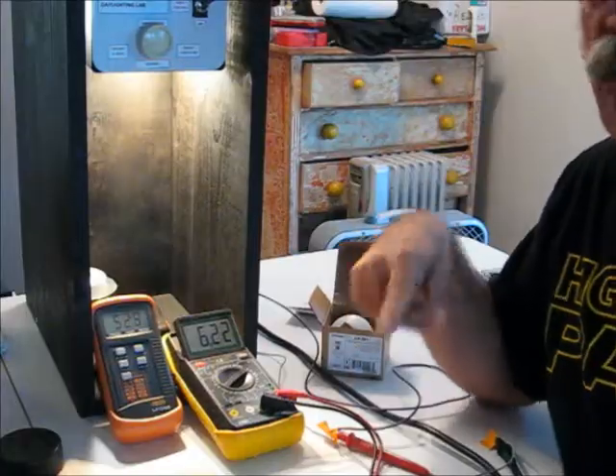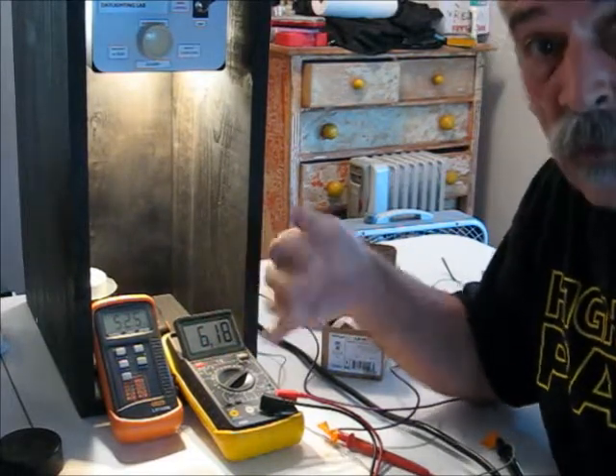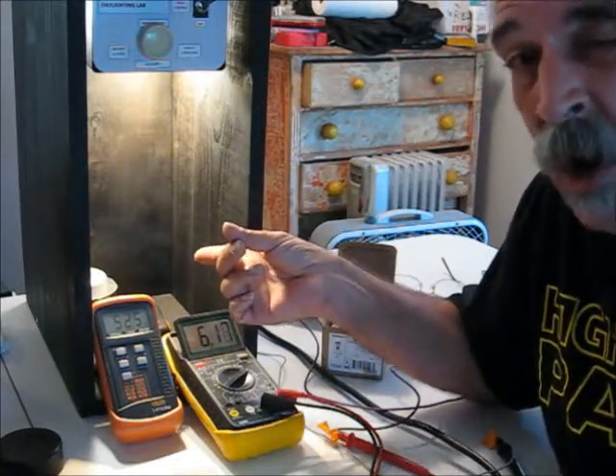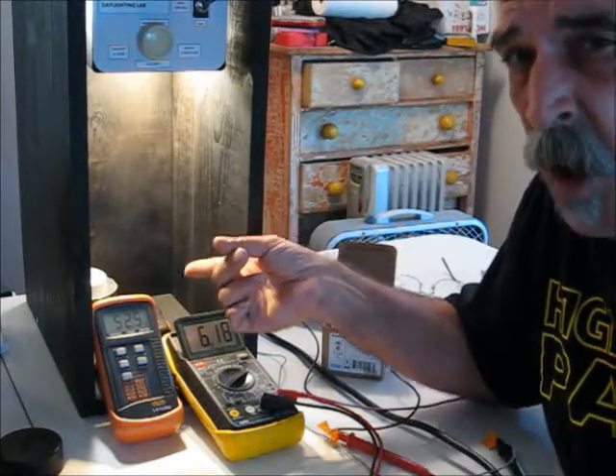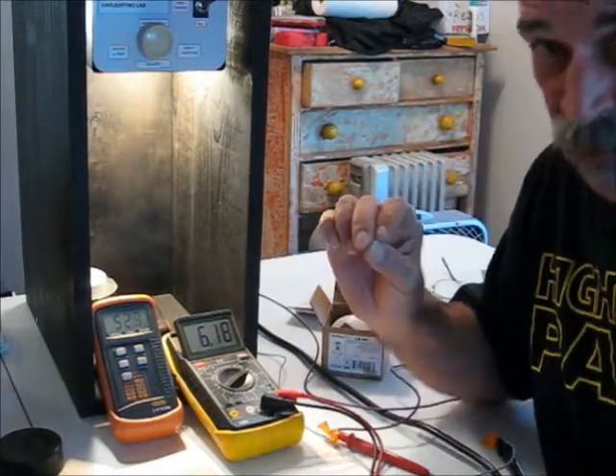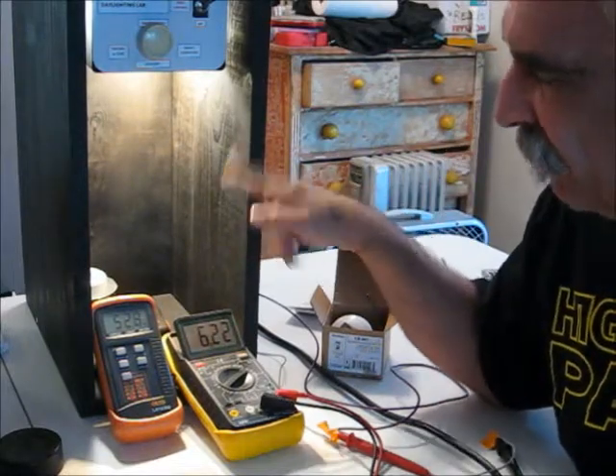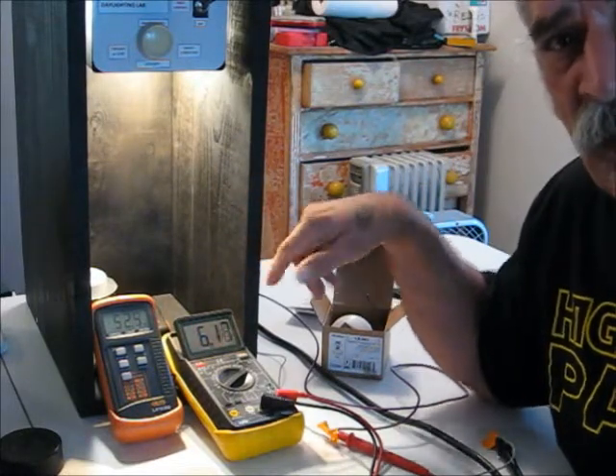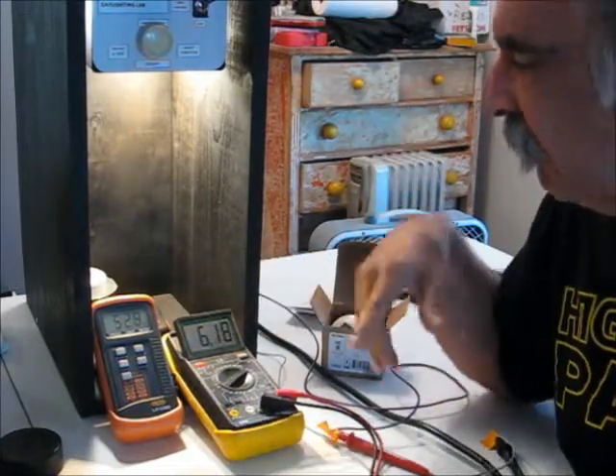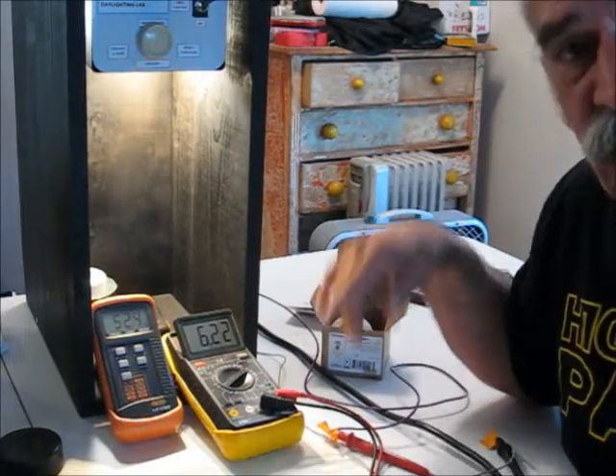Daylighting. Just a little aside before continuing on these controllers, answering a question: is the LS301 Title 24 compliant in the state of California? It's an interesting question. We have this set up with about 35 foot candles of daylight coming in. It's been set for a partial of 52.5. I'm reading 52.5, and control voltage of about 6.25.